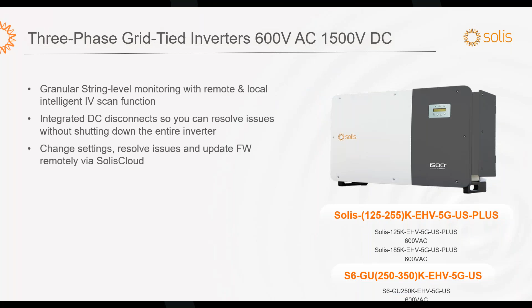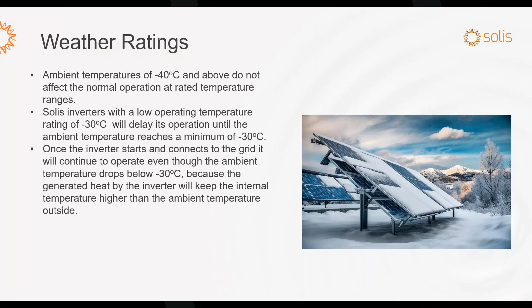Weather ratings. So as you guys know, in Canada, you have some weather as opposed to what I get in Tucson, Arizona. So ambient temperatures of -40 degrees and above do not affect the normal operation at rated temperature ranges. So what that means is Solis has a low operating temperature rating of -30 Celsius. It'll delay its operation until the ambient temperature reaches a minimum of that -30. But once the inverter starts and connects to the grid, it will continue to operate even though the ambient temperature drops below -30 because we generate heat in the inverter, which keeps the internal temperature higher than outside. So again, it helps us perform better in those cooler temperatures.